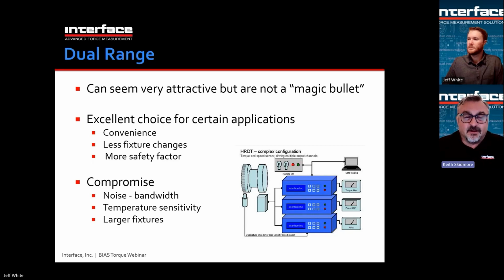And if you're going to do that, it sometimes makes a lot of sense to do it right at the measuring section. So in a dual range torque sensor, there's a strain gauge amplifier right at the bridge, right on the rotating shaft, and the amplification is done there. So you're amplifying as close to the bridge as possible, so you're not amplifying noise that gets in post, anywhere downstream. So dual range can be quite nice for a few reasons. It may be more convenient, with fewer fixture changes. They had two different size motors to test. You can test them in the same setup. A lot more safety factor. Again, if you're not really sure, or you have large spikes, but you also want to measure, say, bearing drag or something in the same test, you might want to have two ranges.